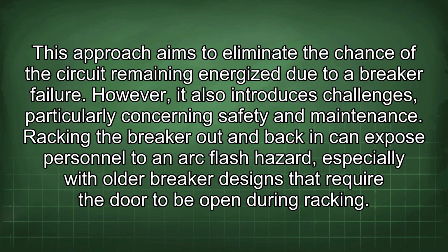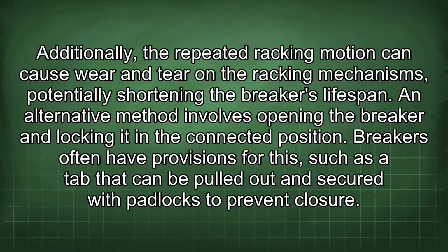Racking the breaker out and back in can expose personnel to an arc flash hazard, especially with older breaker designs that require the door to be opened during racking. Additionally, the repeated racking motion can cause wear and tear on the racking mechanisms, potentially shortening the breaker's lifespan.